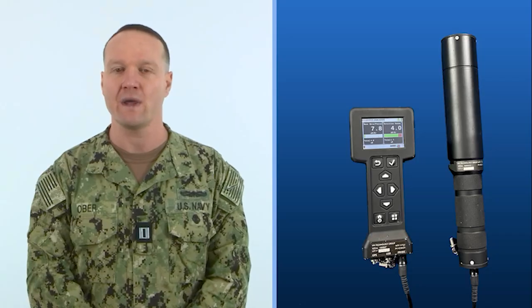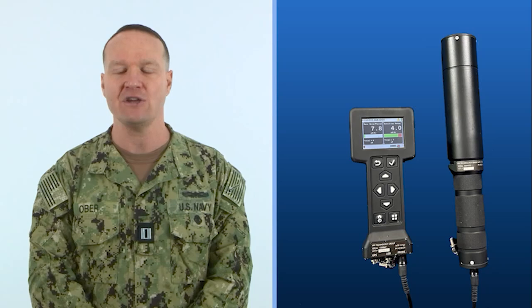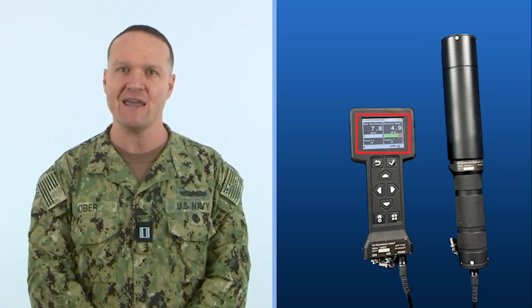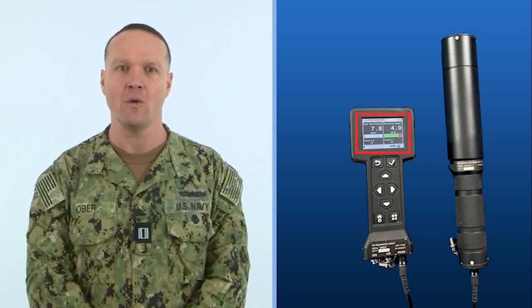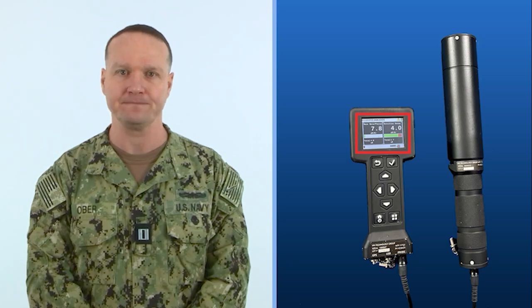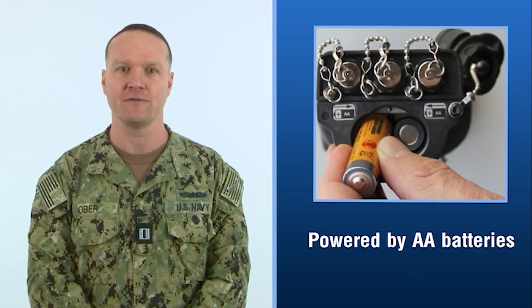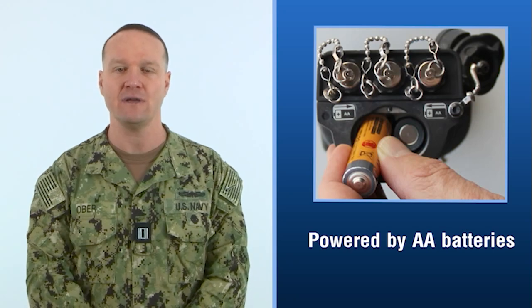Smart probes have a microprocessor, high voltage circuitry, and onboard memory. The type of probe and calibration information for each probe is stored in its memory. When connected to a base unit, a radiation measurement panel, an indication of the type of probe connected, will appear on the base unit home screen. Power or low voltage for a probe is supplied by the base unit via AA batteries, and the probe then generates the high voltage required.